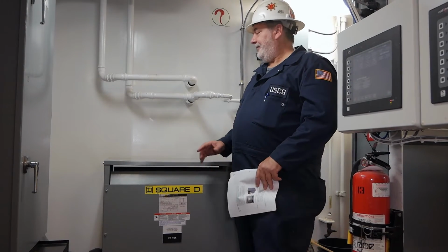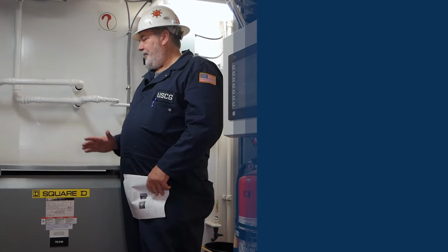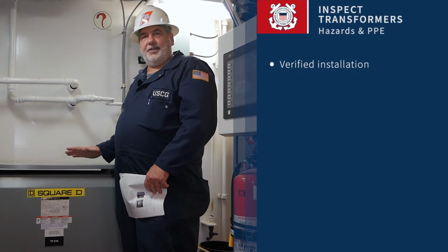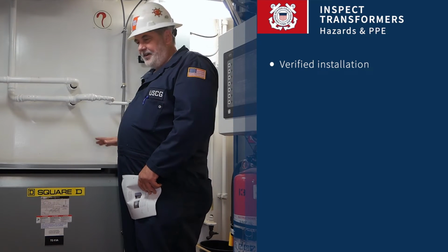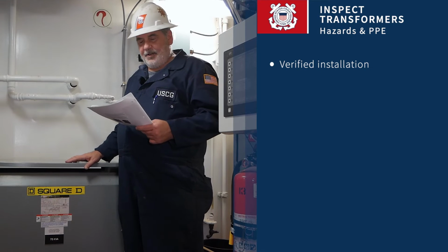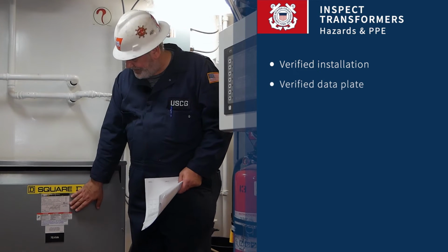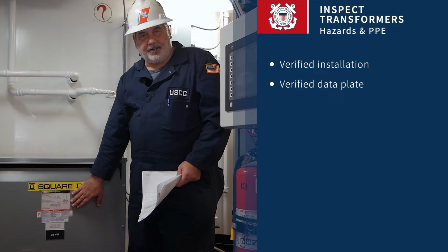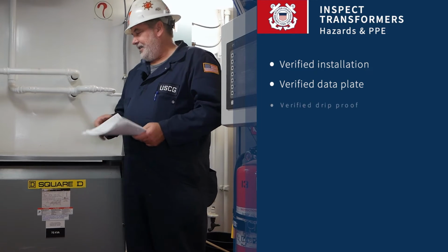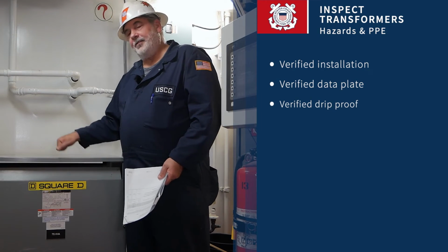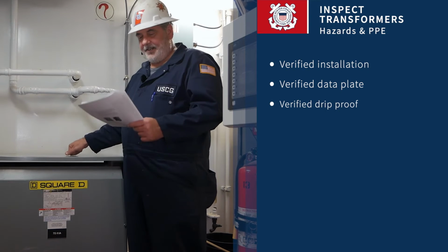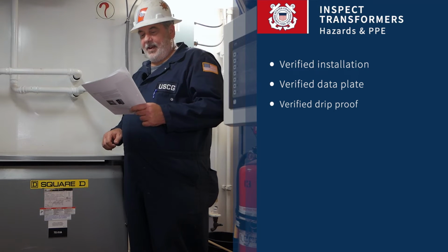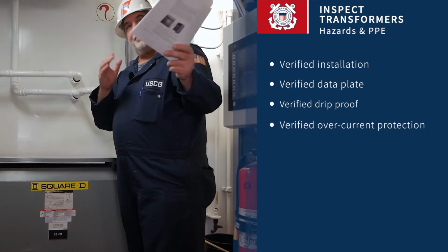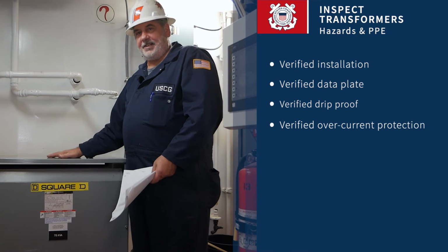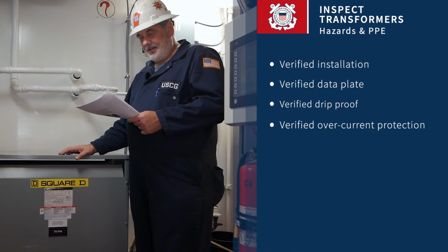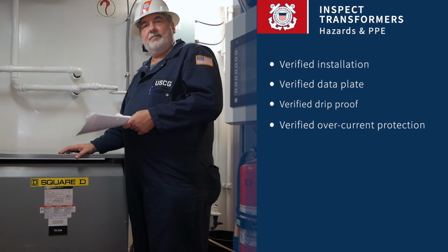So in summary, we were verifying the installation of the transformer, making sure there's plenty of clearances all around it, verifying that the data plate is on it and currently affixed, verifying that the drip-proof nature of the enclosure is still intact, and we are going to make sure that there's a circuit breaker protecting the feed to this transformer.